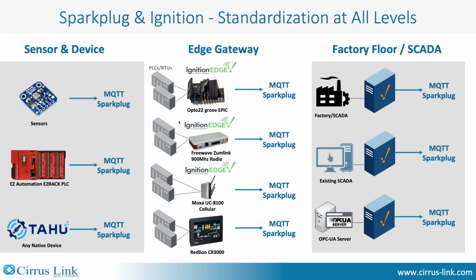On the store and forward, this can be in memory or hard disk. So if there's a failure in the network, let's say a failure at the MQTT server level, it will initiate and start storing all the change events that happen on these tags. In those circumstances, to do your analytics, you don't lose any data. When the network or broker comes back online, the data is published with all the changed data at the timestamp when that happened, and it can backfill in a historian or a process. So you get better AI analytics and don't lose data.